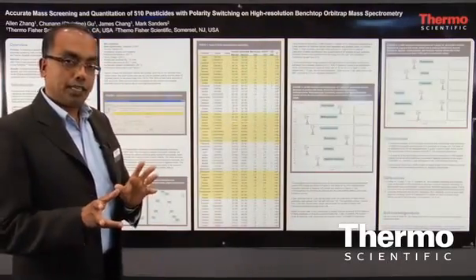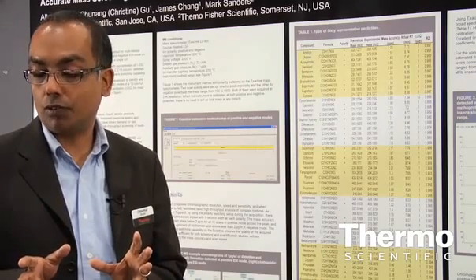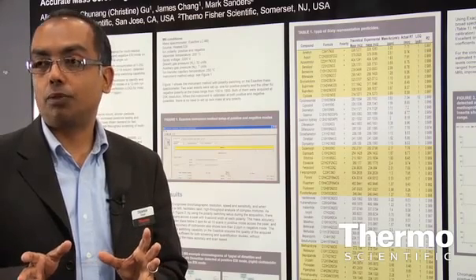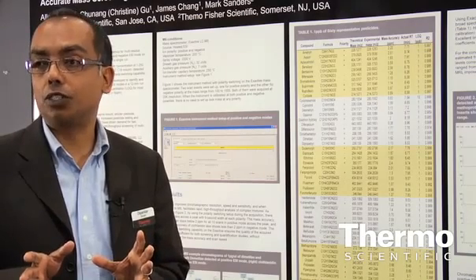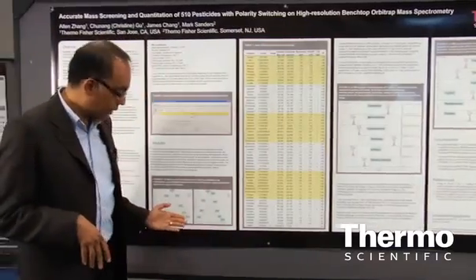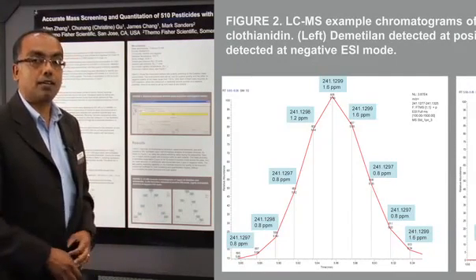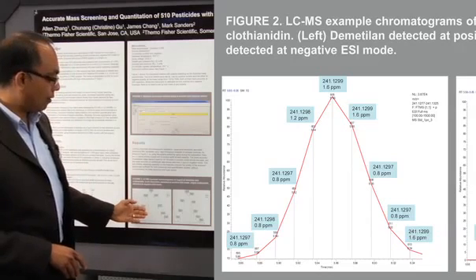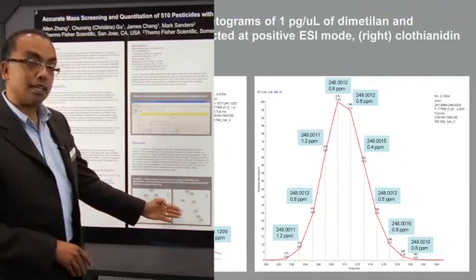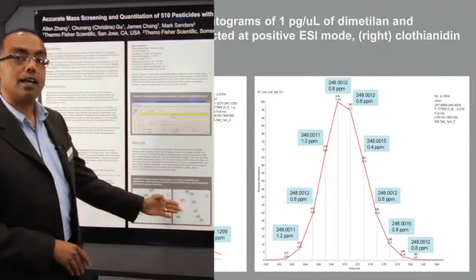Some compounds ionize better in positive and some in negative. Therefore, it is essential for the instrument to be able to do fast polarity switching between positive and negative modes. This graph shows an example of this: the Exactive is able to switch between positive and negative polarities very rapidly. On the left we have a compound being detected in positive, and on the right, in the same scan, we have another pesticide being detected in negative electrospray mode.